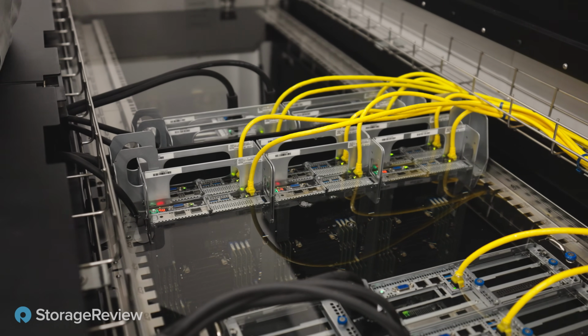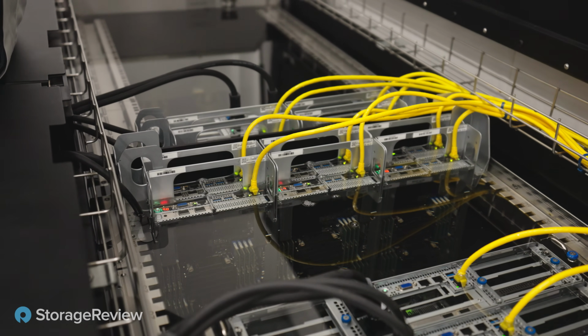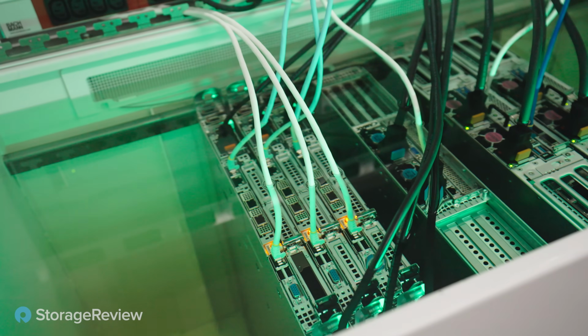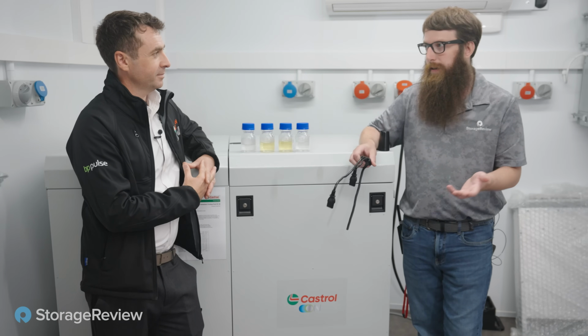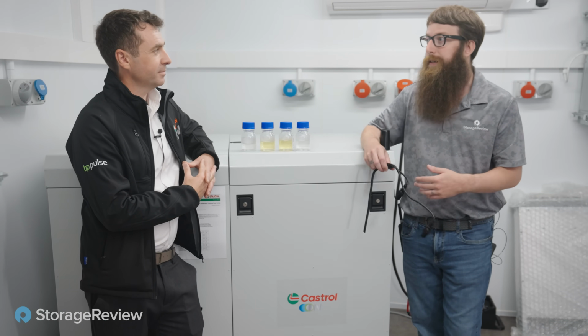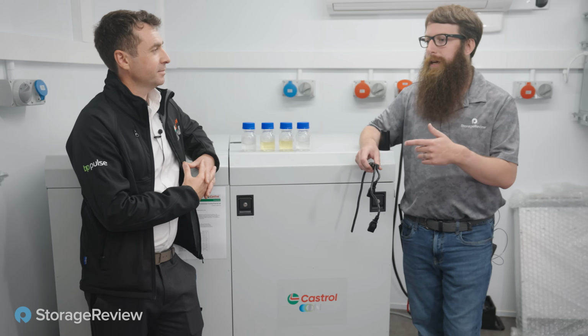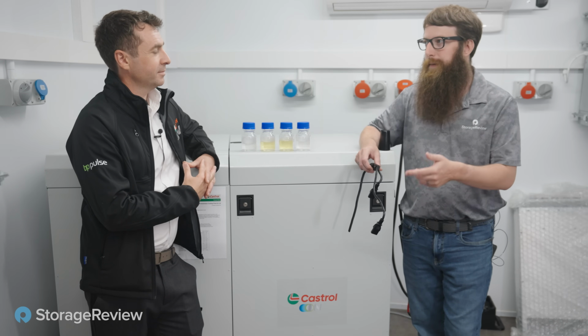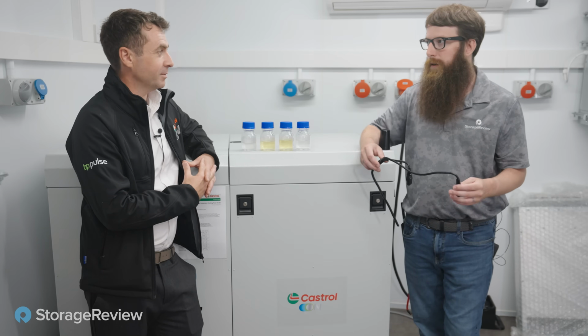People are looking at elevating that further - we're now seeing 50, even 55 degrees. So not only can you save money on the energy side by removing the fans from the system, which in our testing we've seen account for 300-400 watts of fans alone, but the fluid can also operate at a higher temperature so you don't have to spend as much on cooling. Yeah, so it's win-win.